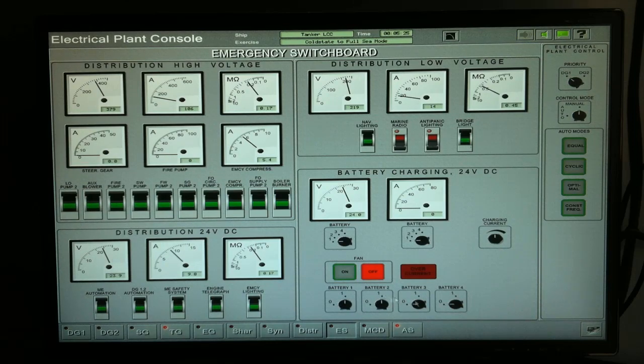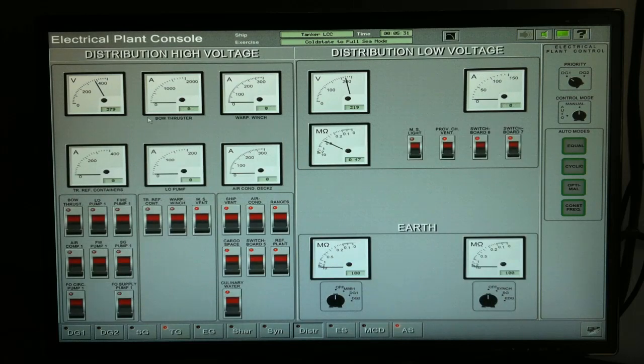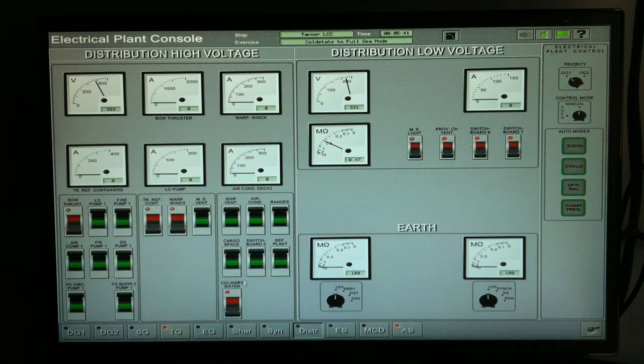Charge your batteries, and proceed also to the distribution panel for high and low voltage. Open these circuit breakers. Okay, leave these 3 circuit breakers closed. We need 2 generators in order to open these remaining circuit breakers.